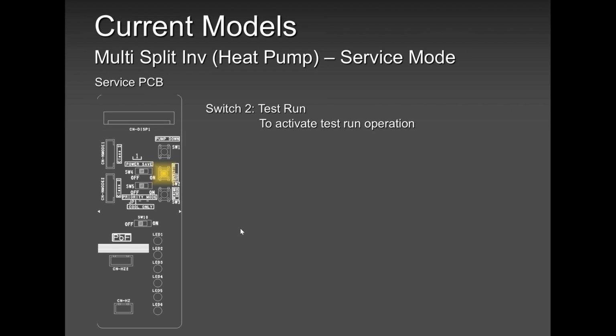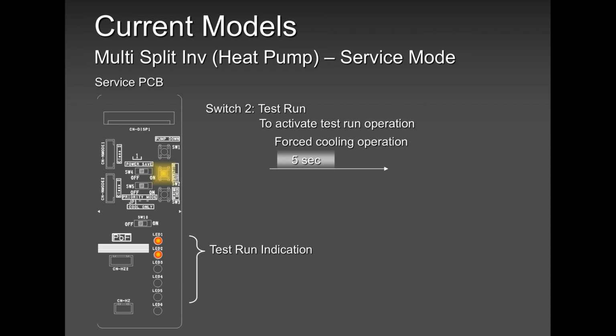Not for commissioning. Do not use test run for commissioning. For commissioning, run one unit at a time. Let it run for 5-10 minutes. You're happy with the first unit, switch it off, go to the second unit. Switch it on, switch off the first unit. Run one unit at a time. I'll tell you, you will not come back. You will not be called back. You will be called back for a different reason, not for cross wiring. So that's basically how you do test run.